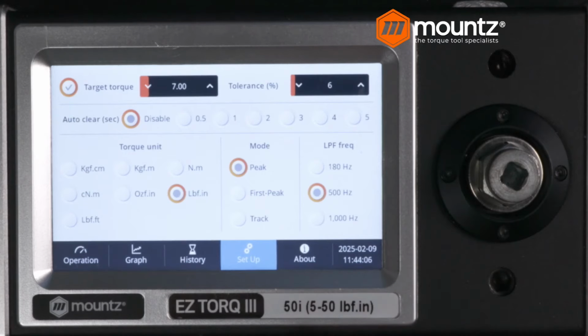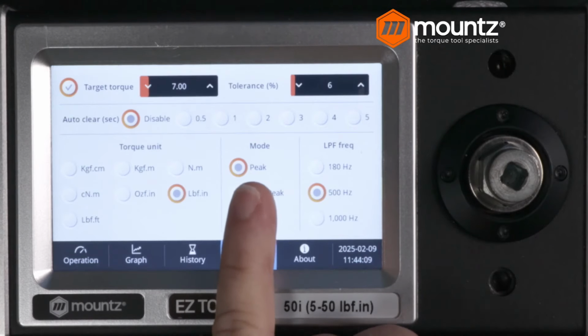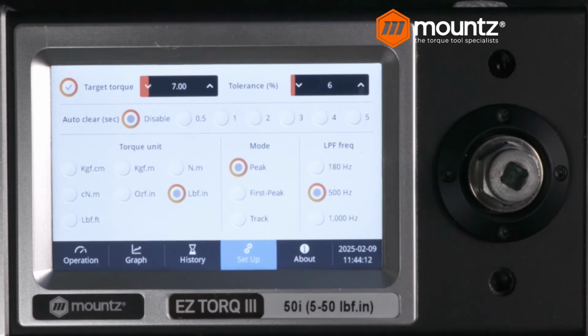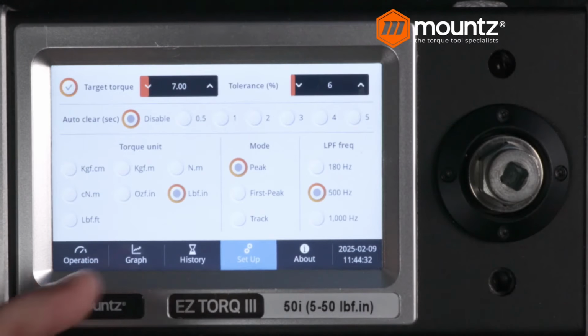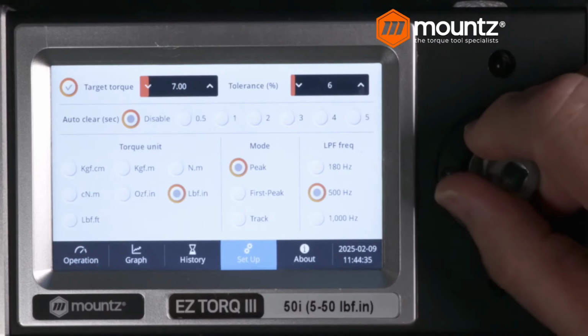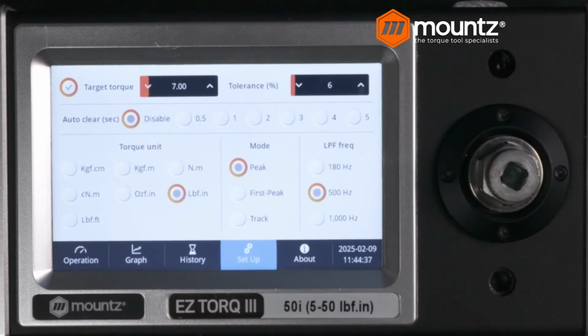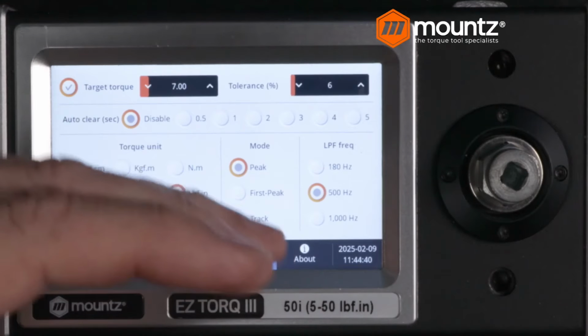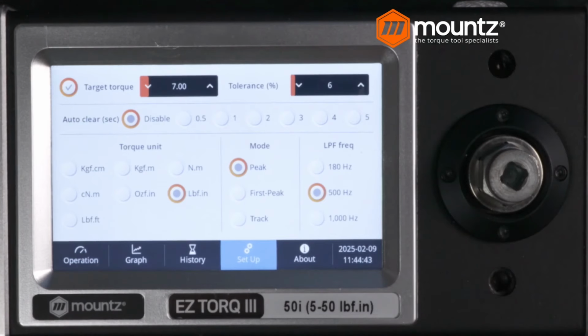And then we have our mode. There are 3 different modes. Peak, which is going to measure the highest peak torque that we see. First peak is done to calibrate click wrenches, and we'll show you what that looks like as we look at our wrench. Then we also have a track mode. This is primarily used for dial type wrenches or digital tools where, as we apply load to the sensor, it's going to constantly be telling us what that value is. Very much like a scale. So as you add weight or take weight, you're going to get whatever that value is on the sensor.